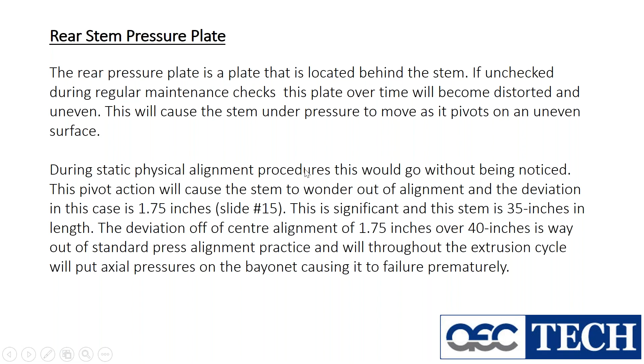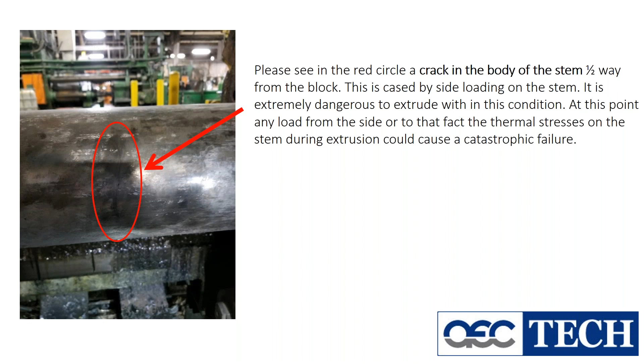This is before we pulled it out. There is an actual crack on the 3 o'clock position of the stem that was absolutely being side loaded by the housing and the container. Remember, that container and the container housing is sitting on 4 axes. It probably weighs cumulatively between 50 and 80,000 pounds. The average 8-inch stem weighs about 750. Stems are designed to have column pressure. They're not designed to have axial pressure on them.